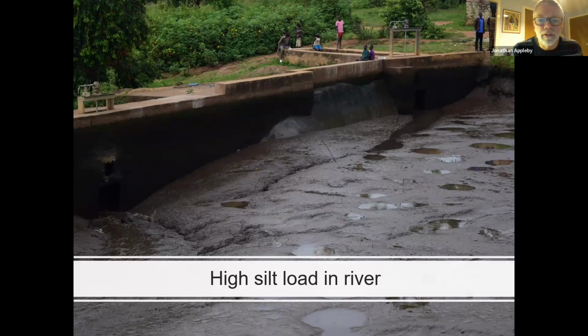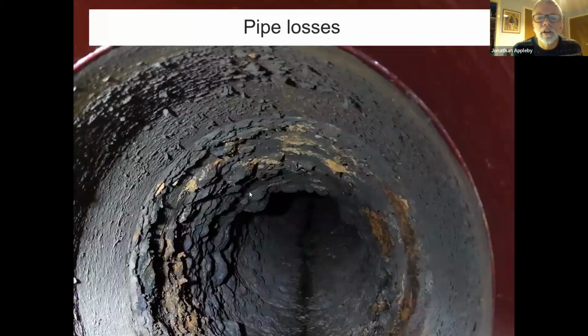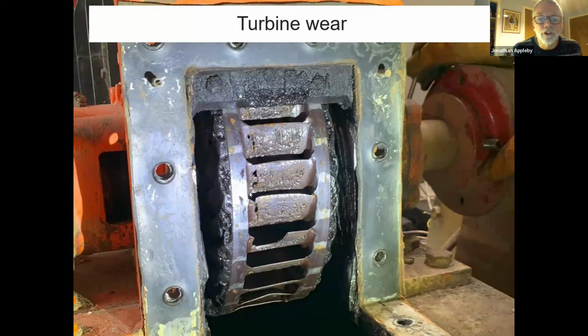Next slide please. Oh, there you go. So the silt load over the 29 years since the turbine was installed caused the damage to this, which is the runner. This is the bit that revolves, that the water hits and turns very rapidly to create the electricity, to generate the electricity. So this has, as you can see, been very badly damaged over the years and just worn away. It may also have been hit by some stones from time to time, looking at it.